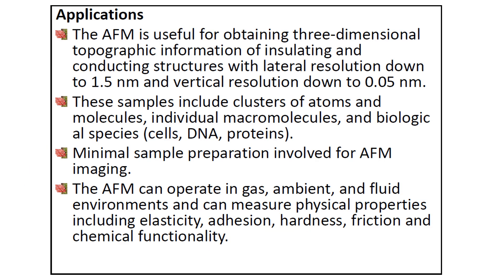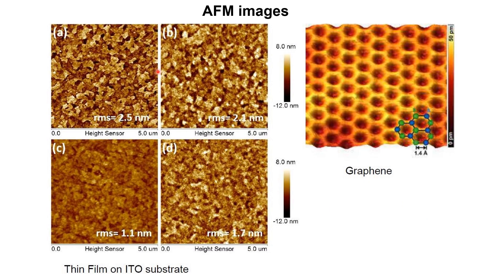The topography of the sample is displayed on a digital screen. AFM is useful for three-dimensional topographical information of both insulating and conducting structures — unlike some instruments limited to conducting samples only. Biological samples such as DNA and any other kind of sample can be scanned using AFM. No special sample preparation is needed and it can operate in ambient conditions. These are typical AFM images where the color scale shows particle sizes, and these particular images are from an ITO (indium tin oxide) substrate.